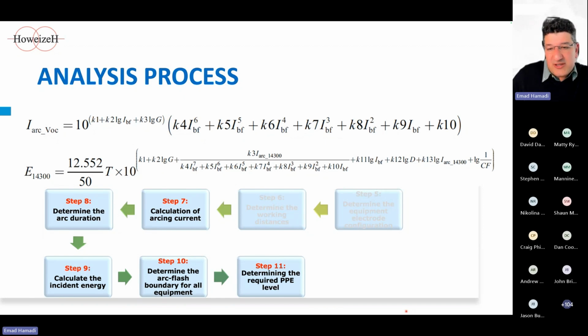And also, when we're doing this calculation, it's important to recognize the multiple arcing locations which can exist in a single piece of equipment. For example, in a single circuit breaker compartment, the incident energy before the circuit breaker, before the contact for the incomer and outgoing, can vary significantly. Therefore, the incident energy needs to be calculated for the worst case scenario, and you just design your arc flash label at the end of the day based on the worst case scenario.